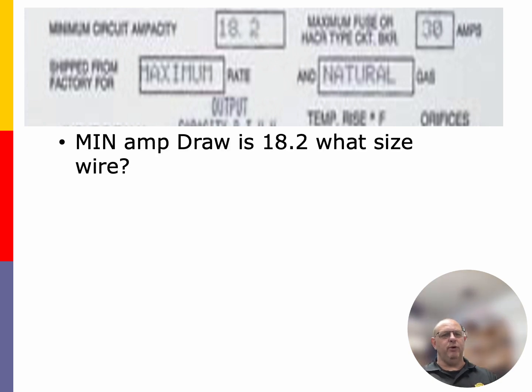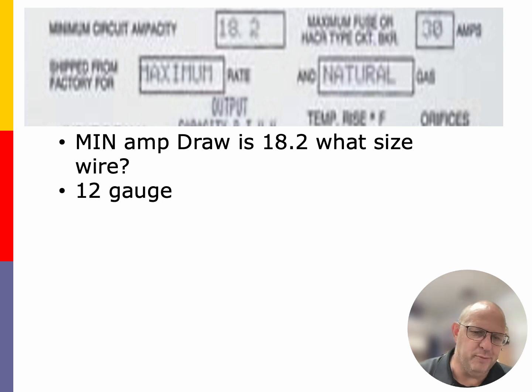Okay, another breakdown of a nameplate that's on a unit. I got minimum circuit amperage, or minimum circuit amps, at 18.2. I got a maximum fuse on this one that happens to be 30 amps. So a couple of questions that I want to ask you. My minimum amp draw is 18.2. What size wire can I use for this particular unit? What you will do is the minimum circuit amps is 18.2 on this one. So I should be able to use a 12 gauge wire, which is good for 20 amps.